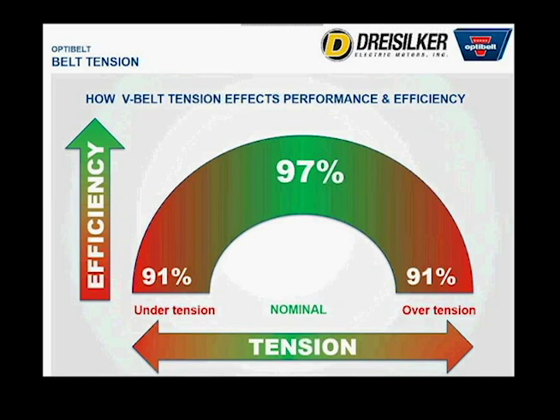Now we'll get into tension. Tension matters because this is where you get your efficiency from. This is where belts either fail early or the motor starts drawing more power than necessary. If you go over tension, it starts drawing more power. If you go under tension, it slips and doesn't transfer the power it needs to the fan or whatever is attached to the motor.